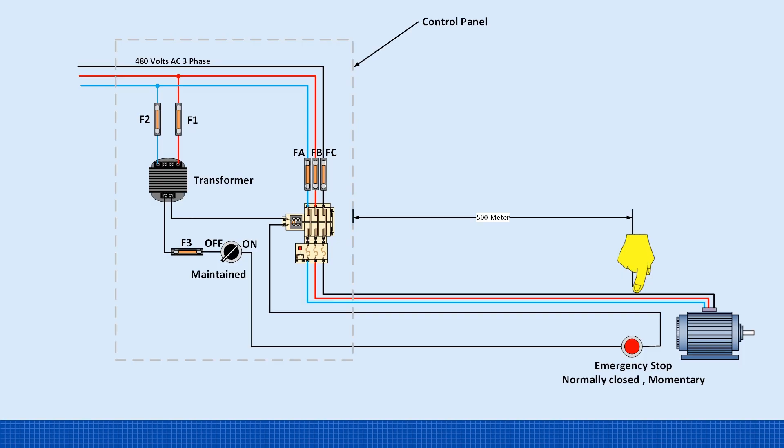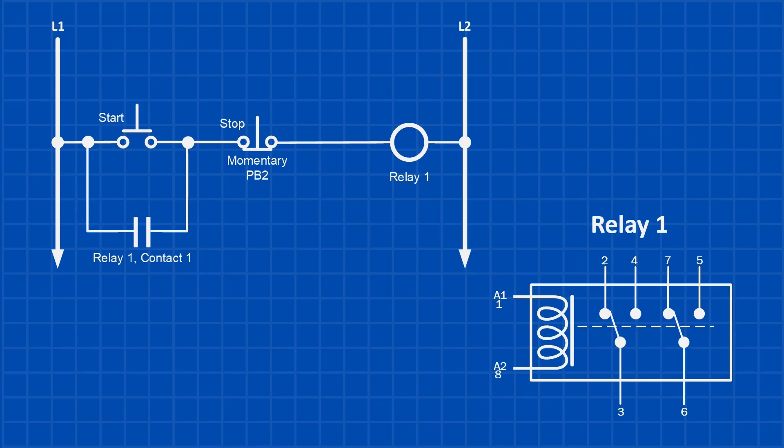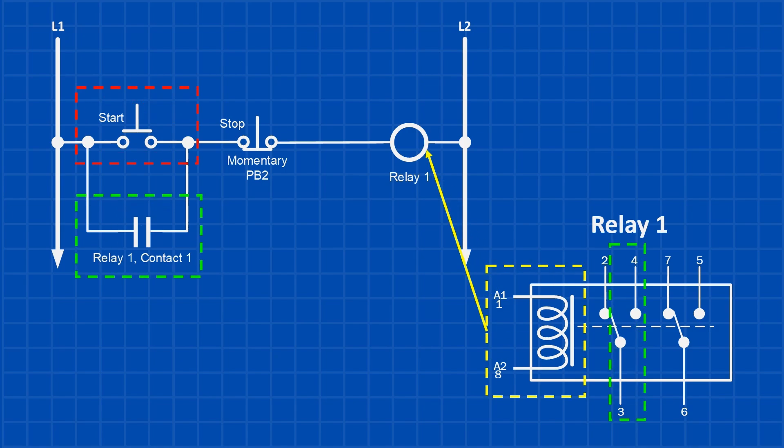So what is a latching circuit? A latching circuit uses a momentary signal, like a push button, to energize a relay, contactor, or motor starter. It also includes a normally open contact from that same relay, wired in parallel with the push button.